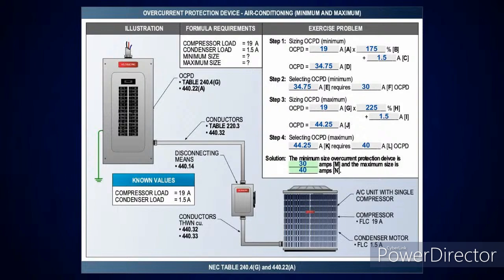Okay. Now, if you go over and look at 430.52C1, does it say the same thing? Sure. You've got your percentage that's done per the table, and if it won't start due to inrush current, then now it's 430.52C1A and B instead of exception 1 and 2. And A allows you to go up to the next standard size without doing any further calculation. And then you've got B, based on what type of device you're using, there's a maximum percentage there. Right. Okay. That's the way we've always explained this.